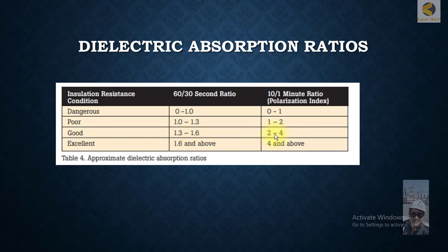If the polarization index is between 2 and 4, or the second ratio is 1.3 to 1.6, then the condition is good.